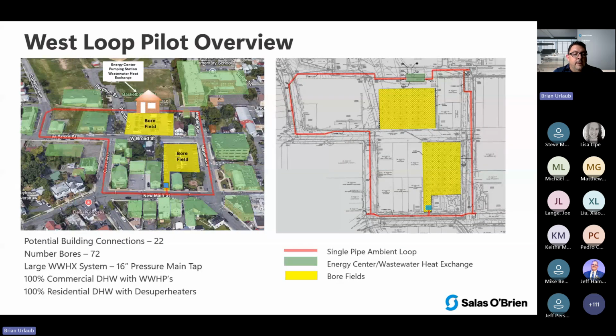So the west loop, which is shown here, we've settled on 2 bore fields and a large sewage heat recovery system. They've got a 16-inch pressurized main that runs right through the site. So we've got a pump house that's shown there on the north end of that bore field. So the manifold for that bore field will be in the pump house. The sewage heat recovery equipment will be in the pump house, and the ambient loop pumps will all be in that pump house. And then there'll be a vault below grade for the other bore field with a pump in it down on the south end of the loop.